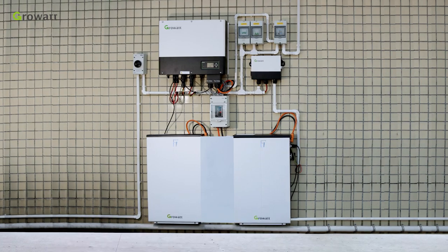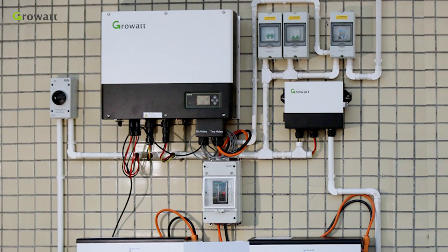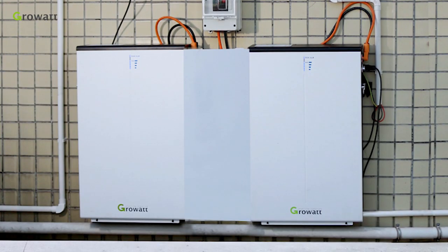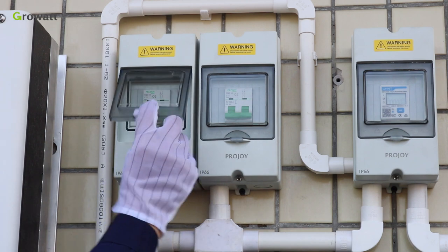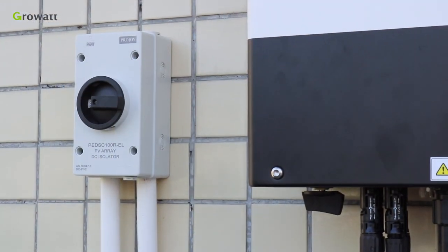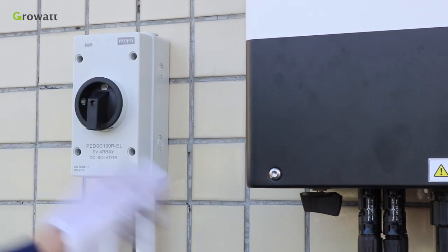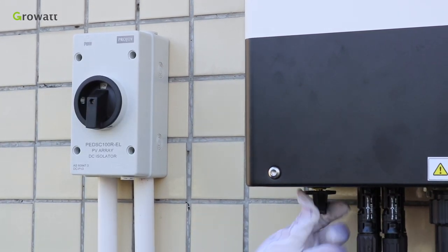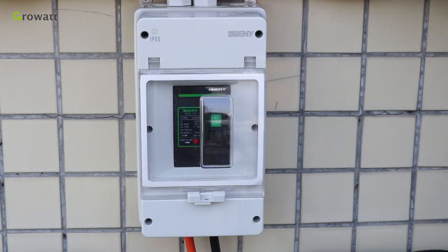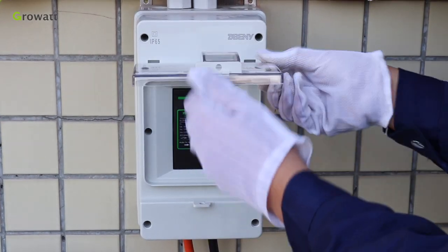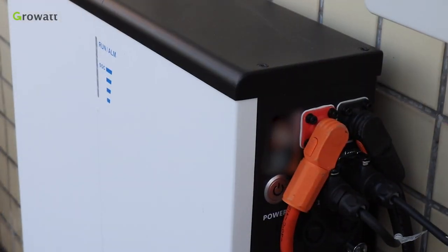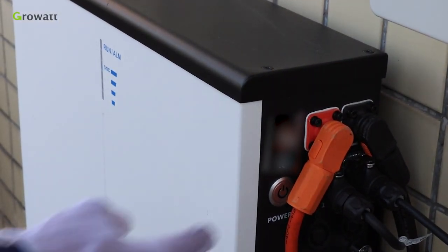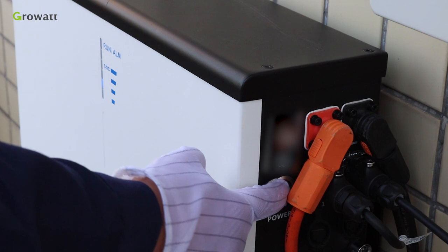After all the installation is finished, here are some steps to power on the whole system. 1. Turn on the AC breaker between the inverter and grid. 2. Turn on the DC breaker of solar input and the PV switch of inverter. 3. Turn on the DC breaker for the battery system. 4. Press the power button of the two batteries within 30 seconds and observe the LED indication finally.